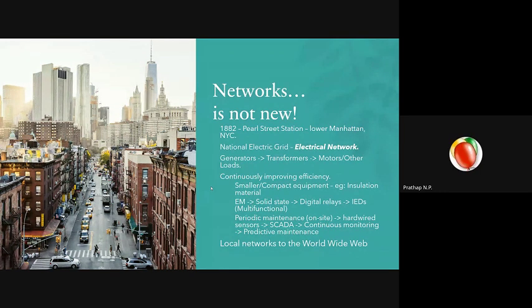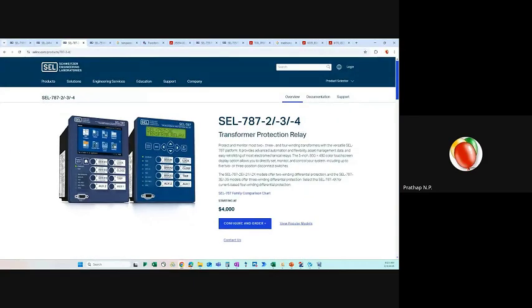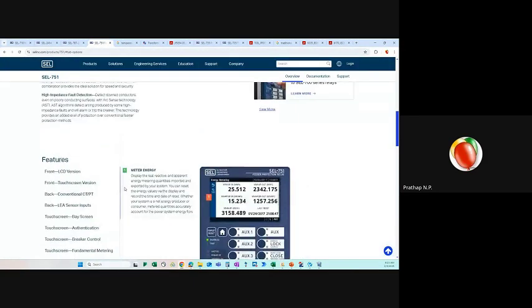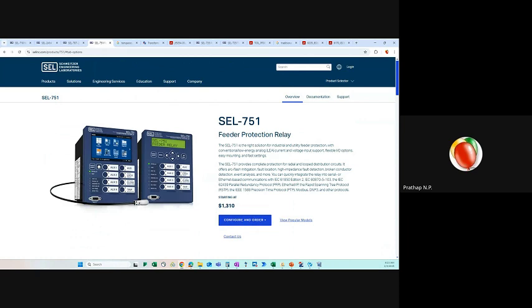Oh, I also forgot to show you arc flash sensors. So this is a feeder protection relay. You see this probe coming out? This is basically an arc flash sensor. When you have a fault, there's an arc flash happening. So this measures the intensity of the light, and there is some logic running which we can program.